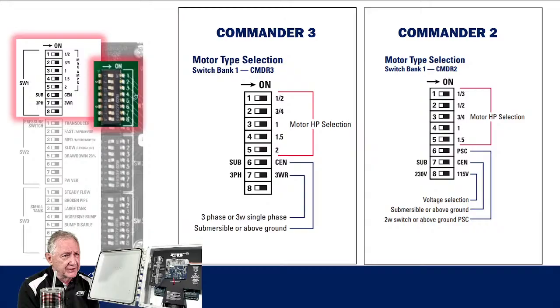If you look at the differences, you still have the horsepowers at the top. Again, it'll only go to 1.5 horse. Position 6 is going to be used for either what we call a 2-wire switch or an above-ground centrifugal motor, particularly one that would have a permanent split capacitor. All we're doing with these dip switches is basically letting the drive know what it is that we're installing. That's basically what we're doing.